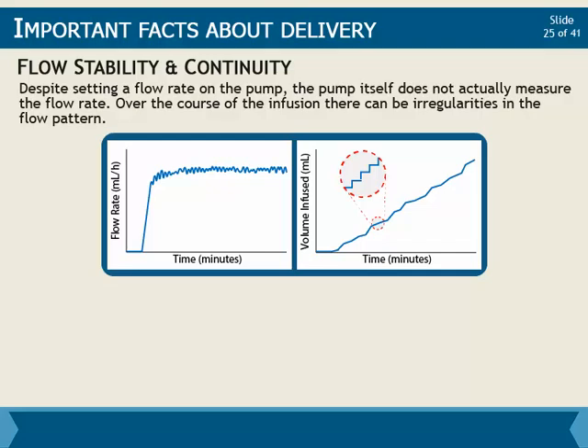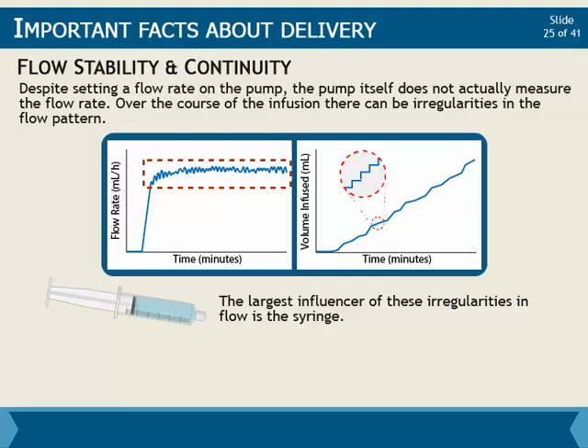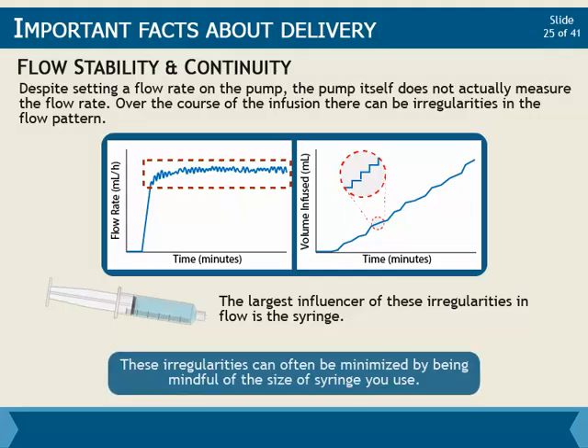Despite setting a flow rate, the pump itself does not actually measure the flow rate. Over the course of the infusion, there can be irregularities in the flow pattern, meaning we don't maintain a continuous smooth flow rate at the programmed rate. The largest influencer of these irregularities in flow is the syringe. These irregularities can often be minimized by being mindful of the size of syringe you use, as we will discuss in the section ahead.